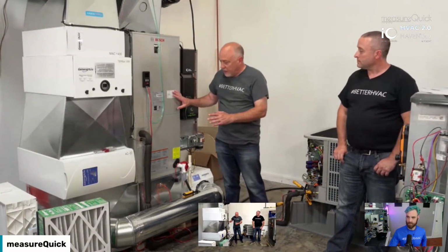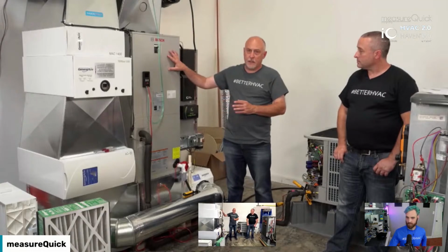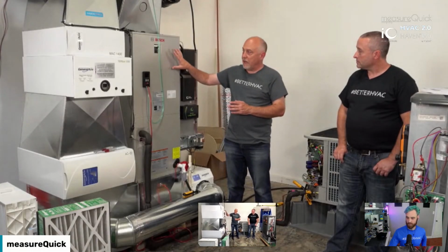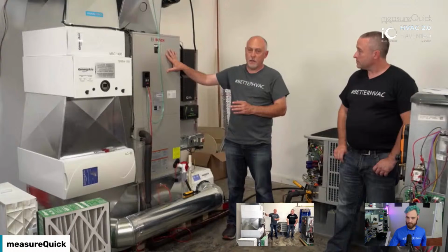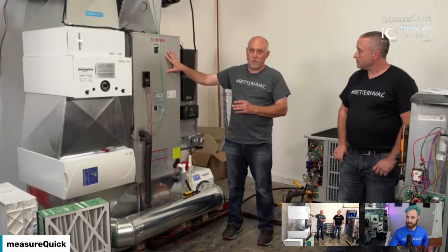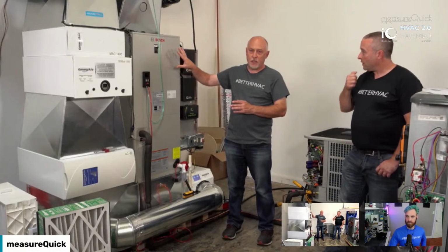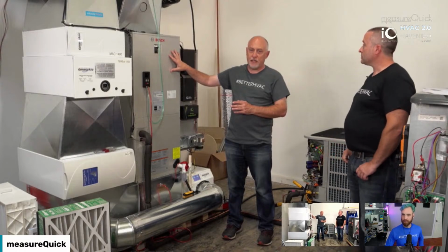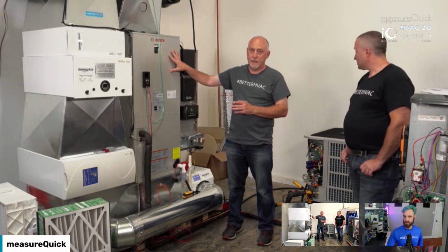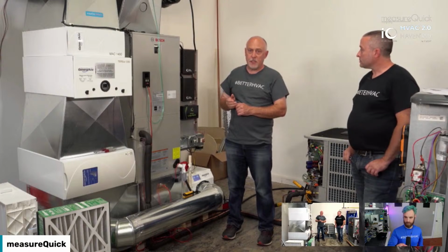Now, the Bosch air handler we have on this, this is a 2-ton air handler. We've got the fans set on low and medium low. And what we're doing here is we don't have a huge space in the back, but we wanted to keep this thing running as long as possible during the day. So we really have it optimized for dehumidification.